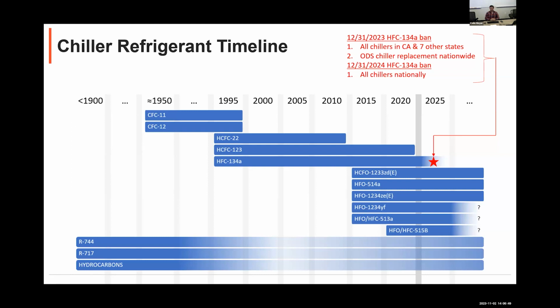And more recently, there have been regulations on refrigerants that contribute to global warming. So refrigerants are classified with their ozone depletion potential and their global warming potential. All of the regulated ozone depleting substances are now beyond their phase out date. So there's not going to be any more chillers in the US that utilize ODS refrigerants. There are still chillers and heat pumps being produced that utilize higher global warming potential refrigerants. One of the common ones is HFC 134A.